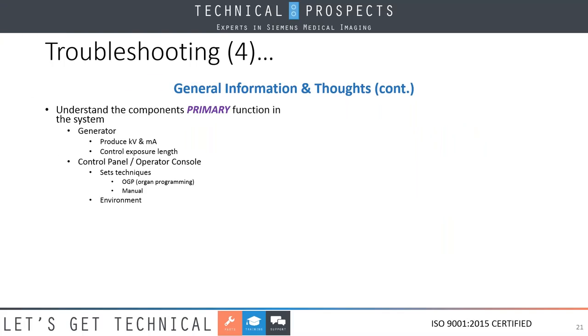So moving on from there, the other thing that's important is understanding the primary function of the system. The generator gives us KV and MA and controls the length of the exposure. That's all it does, all right? Plus monitoring the conditions. Control panel is where the operator sets the technique, either organ programming or manual, all right? They also set the environment. Bucky in, bucky out. Are we shooting the table? Are we shooting the wall stand? These are the things that the system is looking for.